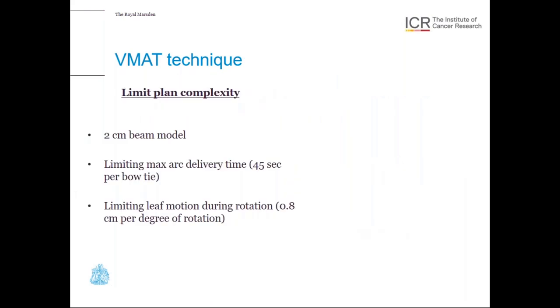Our bowtie VMAT technique aims to limit plan complexity to make aperture shapes and overall delivery as simple as possible. We use a modification of our beam model where MLC leaf pairs must be at least two centimeters apart from each other. We also limit the maximum delivery time of each partial arc to 45 seconds. This has two effects: each partial arc should be deliverable within three breath holds, giving six breath holds total for two arcs — similar to a tangent plus SCF plus post-axilla delivery. Limiting delivery time also limits the optimizer's opportunity to move MLC leaves, making apertures less complex.